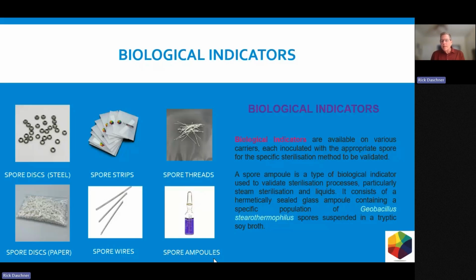So biological indicators are available on various carriers, each inoculated with the appropriate spore for the specific sterilization method to be validated. A spore ampule is a type of biological indicator used to validate sterilization processes, particularly steam and liquid. So you can drop that ampule in liquid. It consists of a hermetically sealed glass ampule containing a specific population of Geobacillus stearothermophilus spores suspended in tryptic soy broth. I wanted to point that out because it has everything already built into the ampule itself, where you're not going to be adding a medium later.